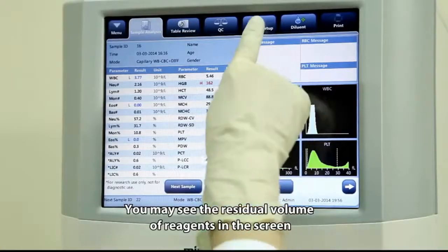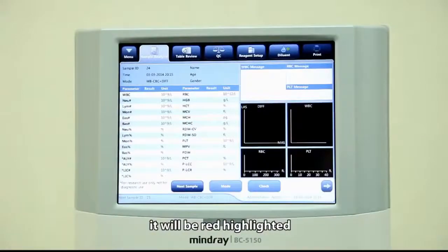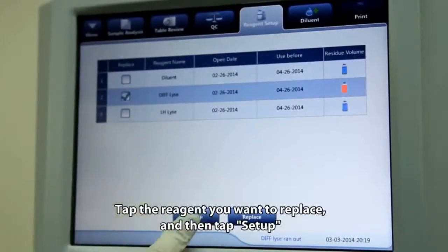You may see the residual volume of reagents on the screen. When the residual reagent volume is reaching the end, it will be highlighted in red, and the BC5150 will give an alarm when the reagent runs out. Tap the reagent you want to replace and then tap Setup.